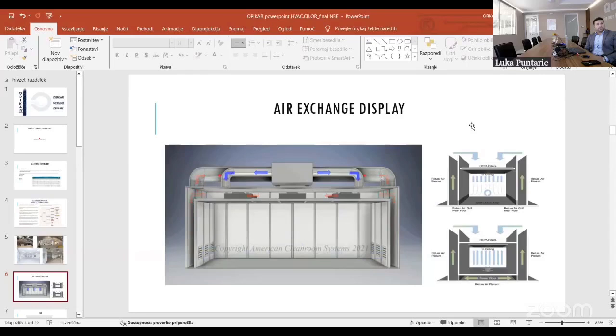Of course, it's a lot better to foresee a heat recovery module in the air handling unit, which enables us to make use of the heat of the exhaust air, so we don't need to heat up 100% of the fresh air, but can use the heat potential coming from the room. So we always have part recirculation and part fresh air. Fresh air is very important to maintain the overpressure in different clean areas. So this is always a game of overpressure and negative pressure.